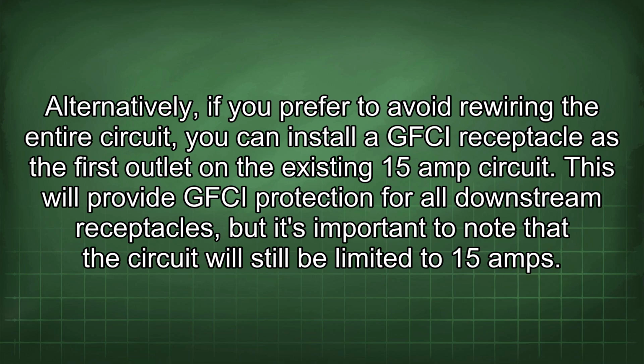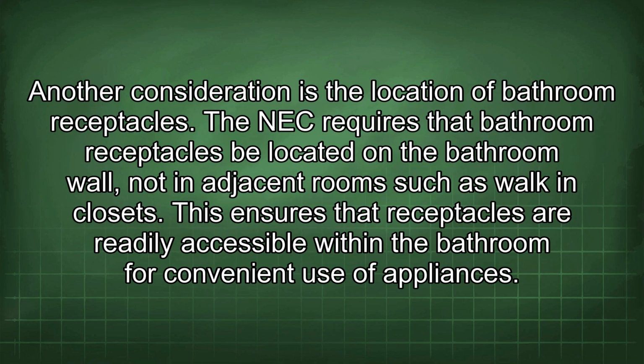Alternatively, if you prefer to avoid rewiring the entire circuit, you can install a GFCI receptacle as the first outlet on the existing 15-amp circuit. This will provide GFCI protection for all downstream receptacles, but it's important to note that the circuit will still be limited to 15 amps. Another consideration is the location of bathroom receptacles. The NEC requires that bathroom receptacles be located on the bathroom wall, not in adjacent rooms such as walk-in closets. This ensures that receptacles are readily accessible within the bathroom for convenient use of appliances.